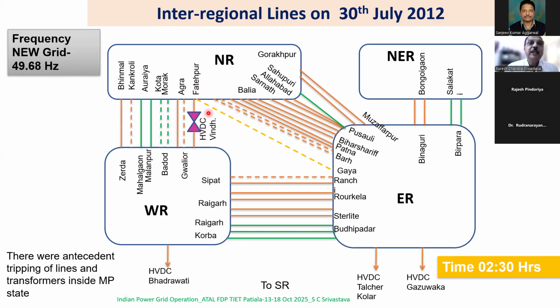Unfortunately, many lines tripped at that time because of some fault, and some of them were also out for maintenance. The dotted lines were not there, the 400 and 765 kV lines. Finally, at the last minute some tripping took place. The Agra-Bina line and the Gwalior-Bina line were overloaded. First day about 1400 megawatt power was flowing through this, and its SIL is about 600, 700 megawatt. So it was overloaded, but you cannot prevent it because of the low cost through the UI route they were drawing.